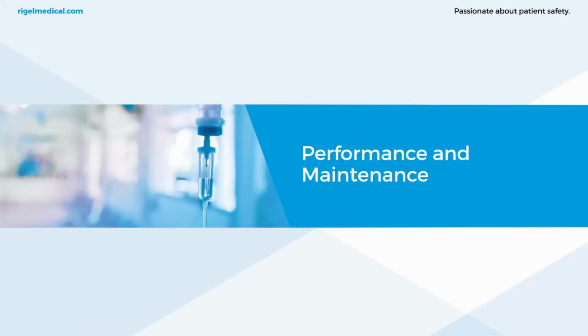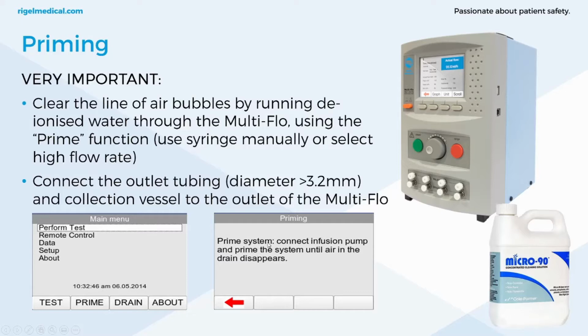So this is the volumetric second generation of how we've incorporated this into the Multi-Flo for flow rates. So before going on to testing, it's important to look at the performance and maintenance with infusion pump analyzers. They are susceptible to certain things. You are dealing with fluids which can cause issues with the analyzer itself. So priming is very important. We've got a performance and maintenance manual for the Multi-Flo. You can find that on our website, which goes into a bit more detail. But I think we should go over this just because it can sometimes get overlooked, and it's really important for looking after the instrument and prolonging its life cycle without having to go back for any repairs, which can be not very cost effective. You get downtime on your instruments, so it's about prolonging the life of your instrument.